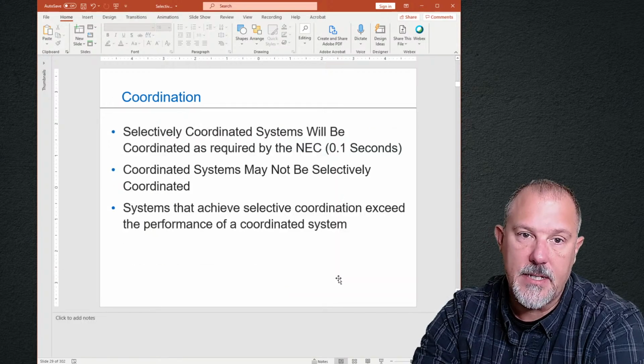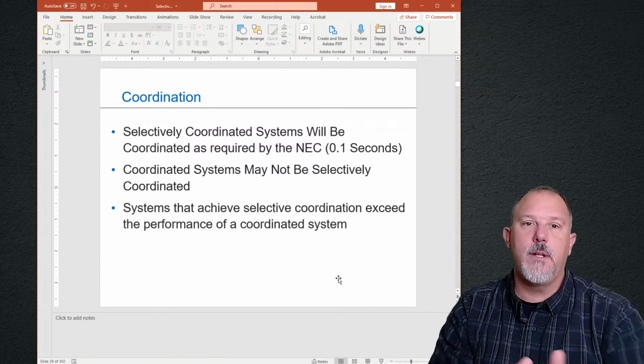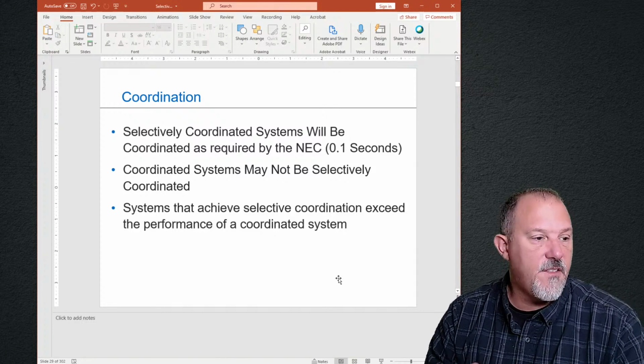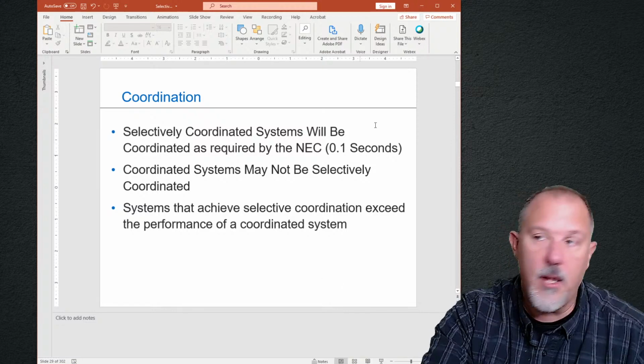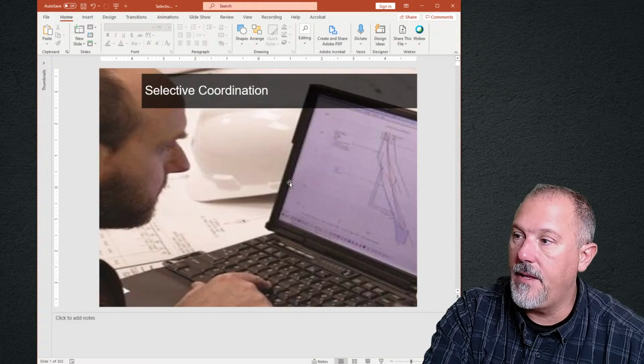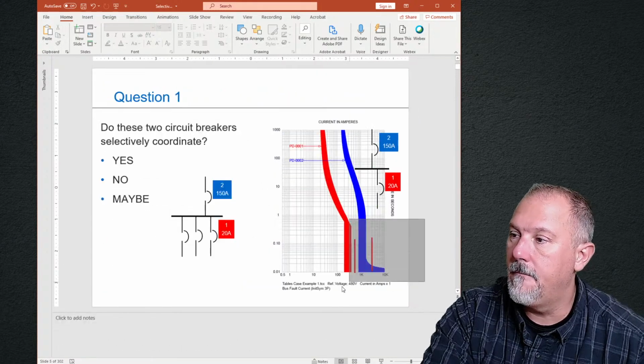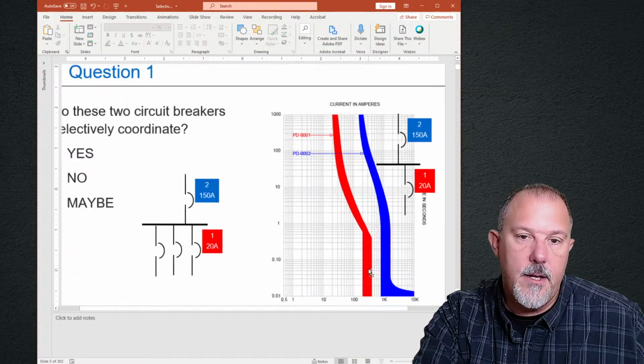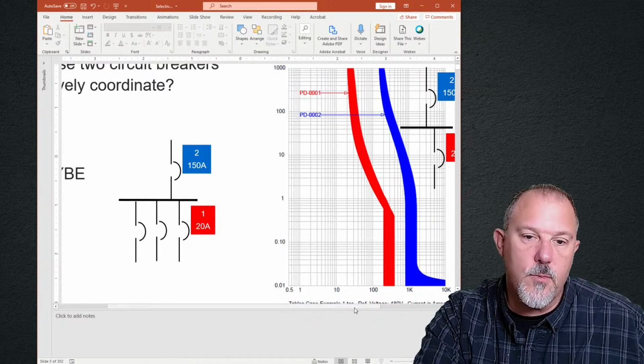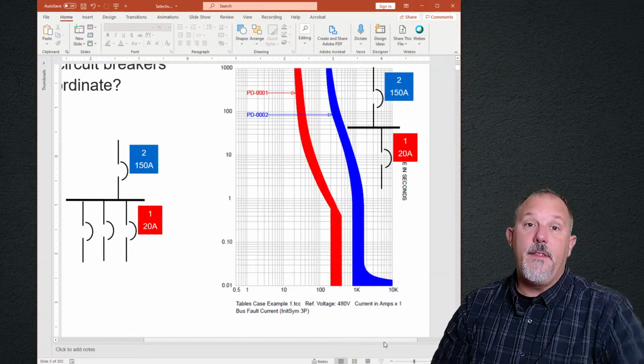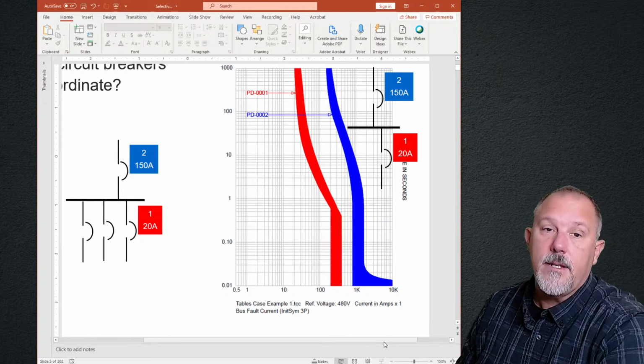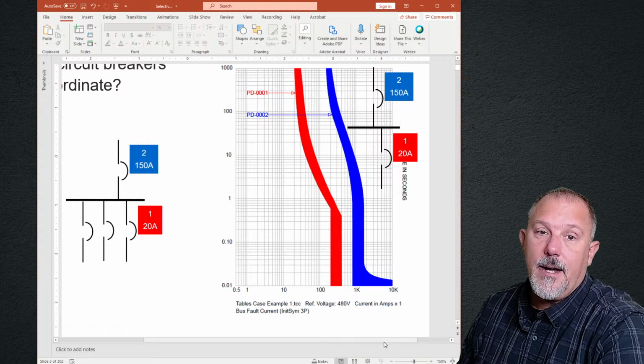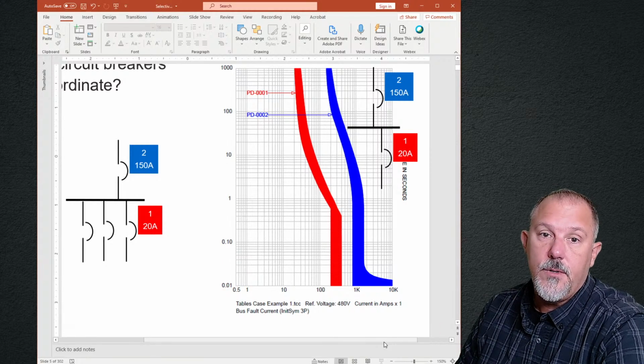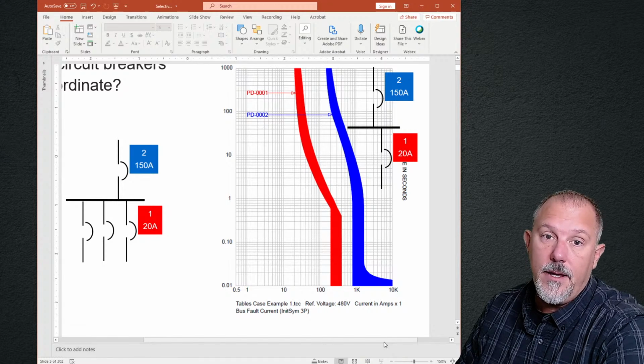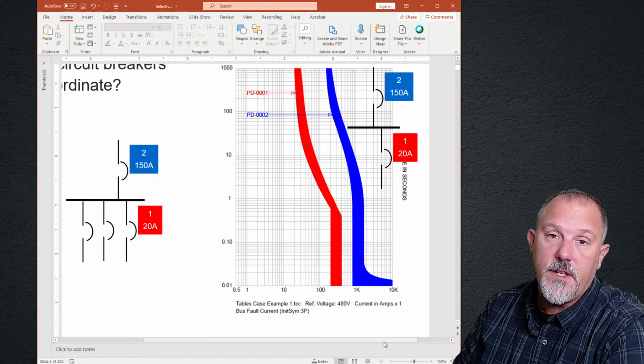So I think the whole introduction of 0.1 seconds really confused a lot of individuals. I think that there are a lot of people that will look at these curves right here and they will say, gosh, they are beautiful. They selectively coordinate. Look at the separation of curves all the way down to 0.1 seconds. And they stop right there. And they are technically incorrect because I need to evaluate both of those overcurrent devices with regard to current. And in the case of selective coordination, it's the maximum three-phase bolted fault current.